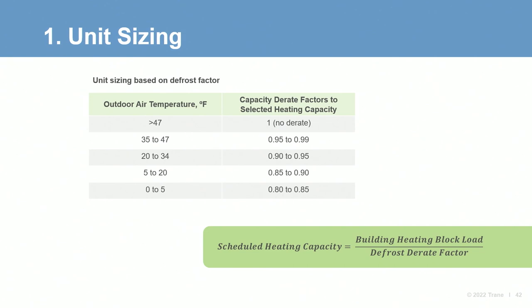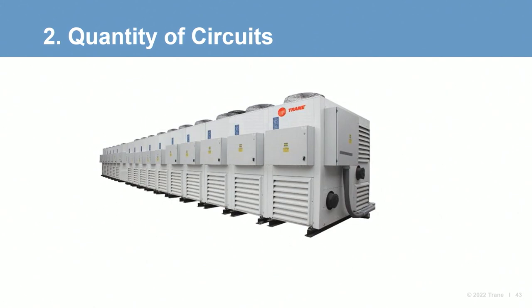The table shown here offers suggested heating capacity derate ranges based on operating outdoor air temperature. As Charlie will discuss in the unit sizing exercise, the derate factor should be applied to the required unit design capacity and selections to be made based on this. The equipment schedules and schedule notes should clarify this has been done. This will help ensure equipment selections include the proper defrost impact. Second is the number of units or circuits. A designer could specify extra modules, extra units, or select units with more circuits or compressors to address defrost. With more circuits in the system, the impact of defrost could be minimized.